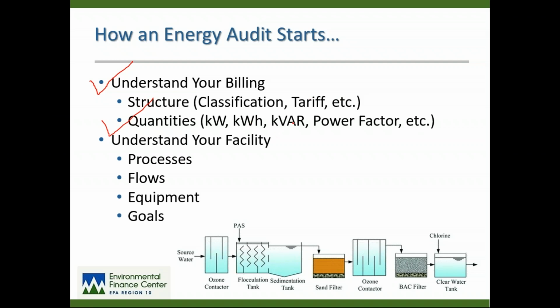The second step, and probably the most important one, and maybe the most time consuming, is to understand your own facility. Now, most of you already do, especially if you are operators or facility managers. Understand your own processes, your own flows, what your requirements are, your peak daily demand, your peak hourly demand. Understand your equipment, especially how old it is and how well it's running and how well it's controlled. And then understand the goals that you want to set. A typical goal would be you go to your board or your decision makers and say, we need to reduce energy costs by 10% within the next 12 months. That would be a concrete goal that's pretty achievable most of the time when we're doing these audits.